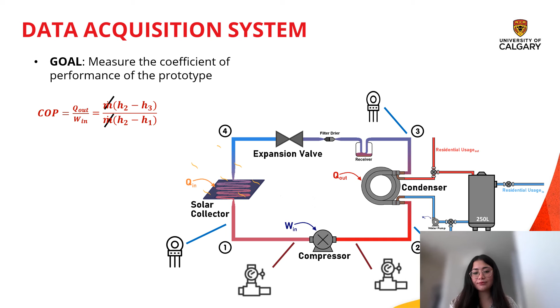The specific enthalpy, H in this equation, can be determined easily from property tables at measured temperature and pressure values. Temperature sensors at 3 locations, 1, 2, and 3 on this diagram, as well as pressure sensors at 2 locations, 1 and 2, the suction and discharge of the compressor, were used to extract this data.